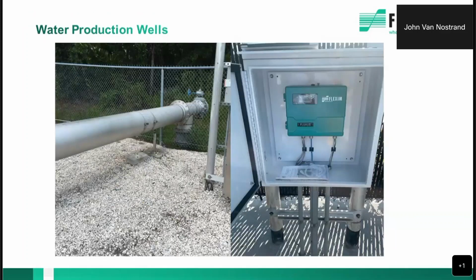Here's a drinking water production well. This is a 12-inch stainless steel well. We've got the CDM transducers. This is a well that is full of heavy manganese. So the Magmeter failed. There was a Magmeter on this location. Over time, it just failed, and they would have to take it out.